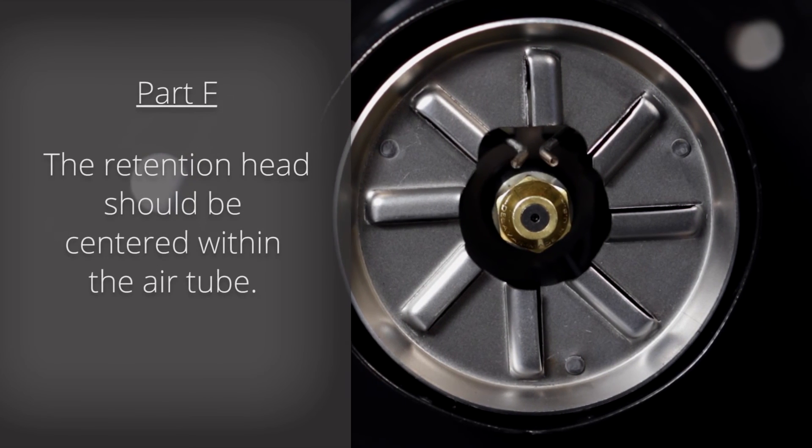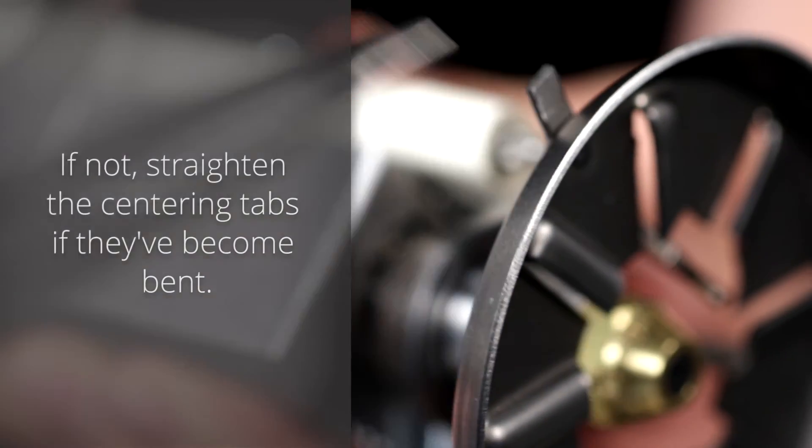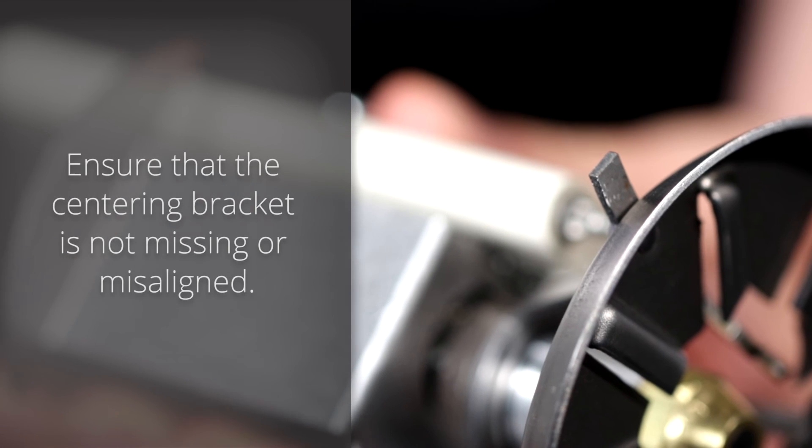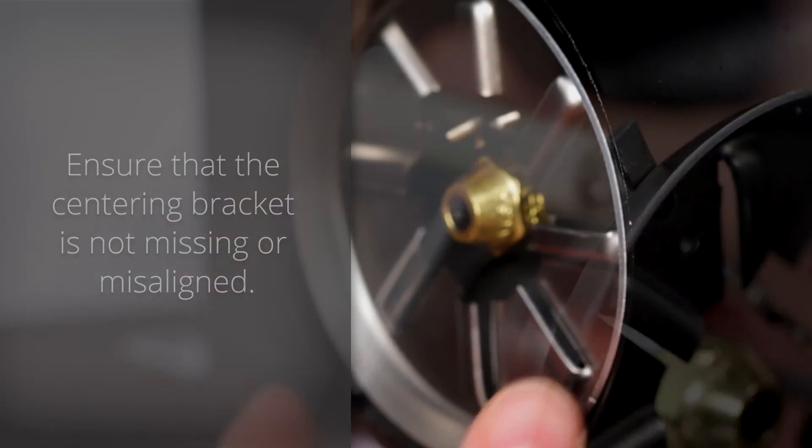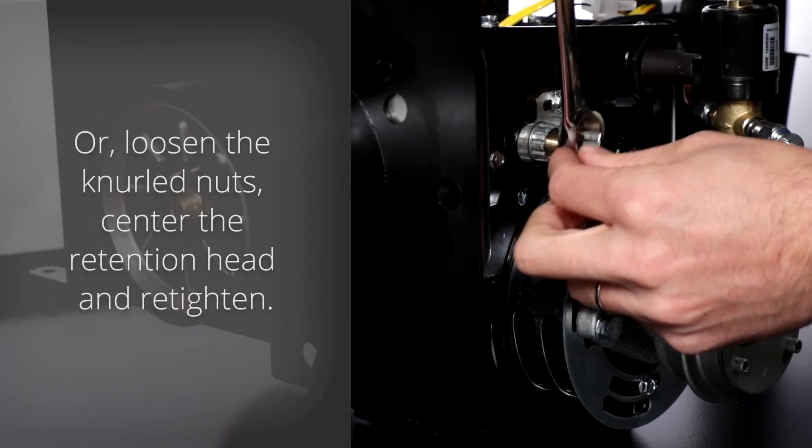Part F: The retention head should be centered within the air tube. If not, straighten the centering tabs if they've become bent. Ensure that the centering bracket is not missing or misaligned. Or, loosen the knurled nuts, center the retention head, and re-tighten if necessary.